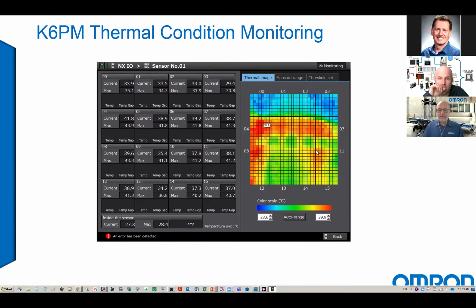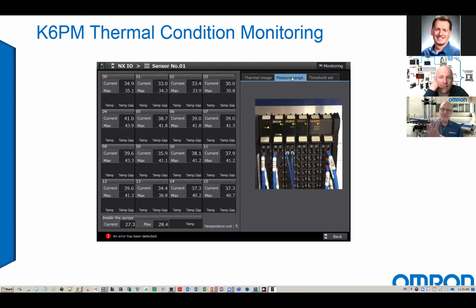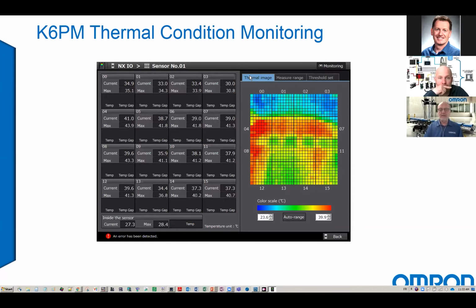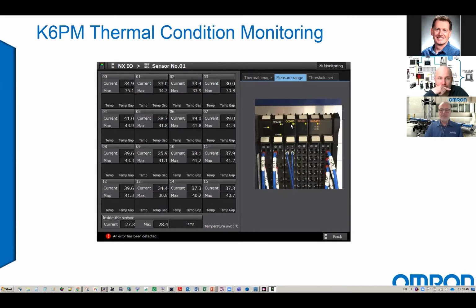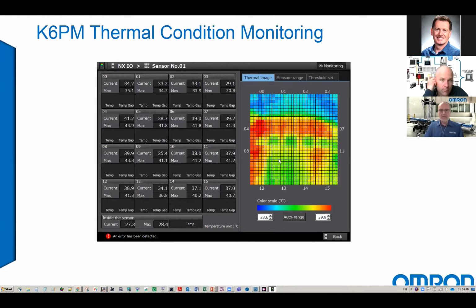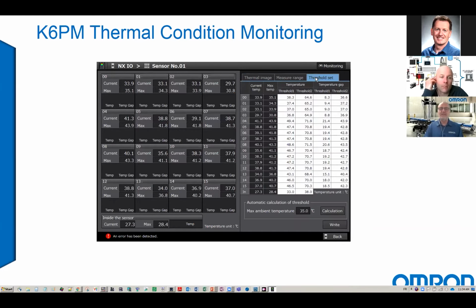But what are we looking at? The camera is looking at something inside my control panel, but if I click on the measure range here, you can attach a picture of the section where the camera is really looking. If I go back to the thermal image, you can see the top of my IO rack is hotter than the bottom, because there are electronics here and LEDs being turned on. These are creating more heat than the actual terminals there. But if there was a hot spot or too much current on this wire and it was abused, then the thermal image would most likely show me a line here showing that these segments are too hot. You can also readjust the ranging to improve your image, and we also have thresholds that can be calculated automatically according to the room temperature inside your control panel.